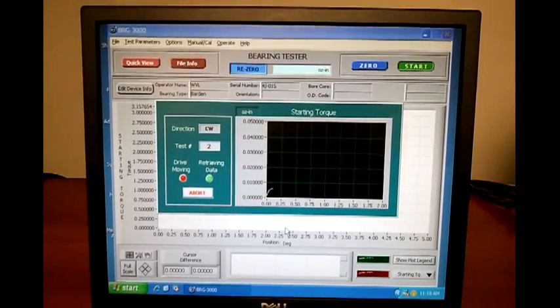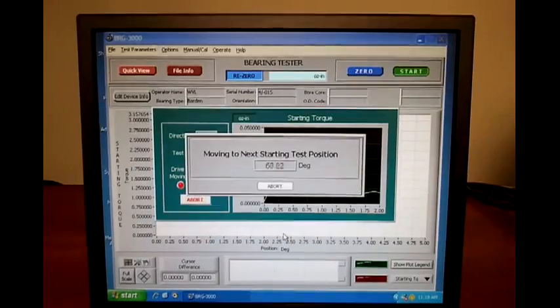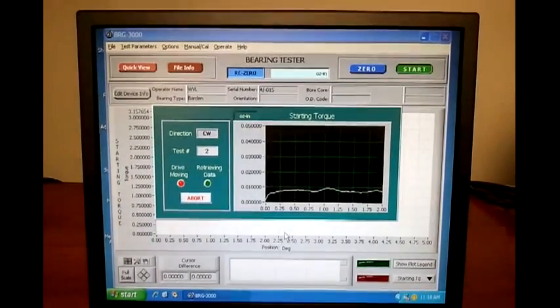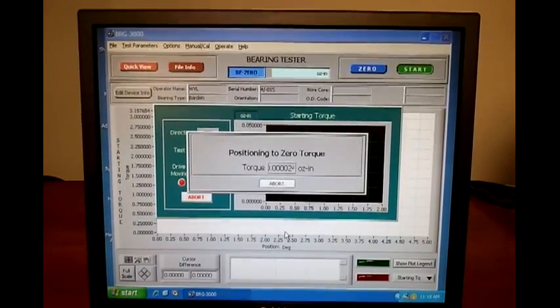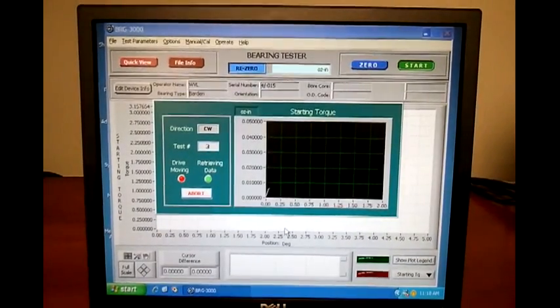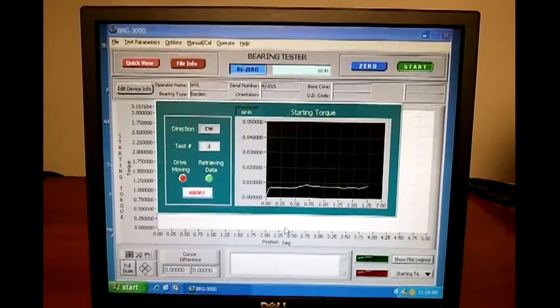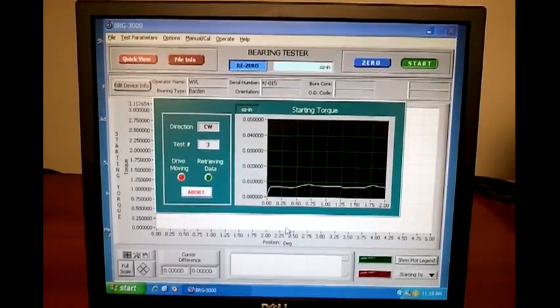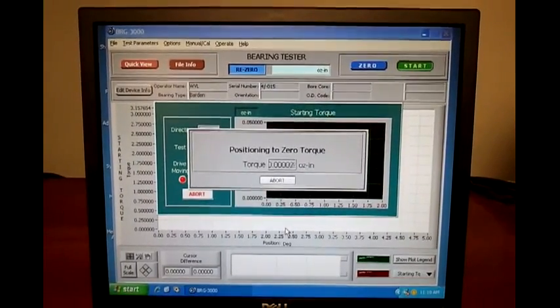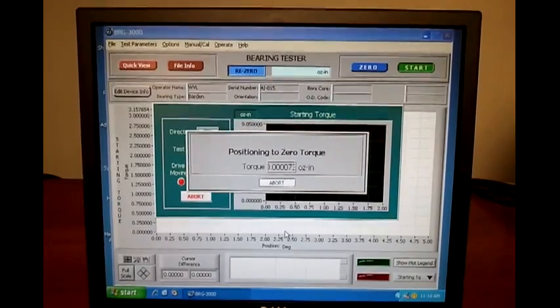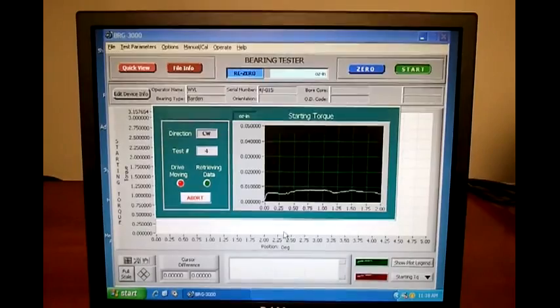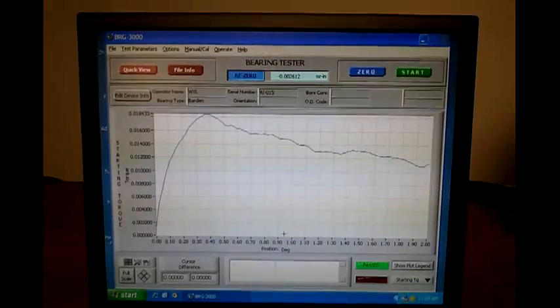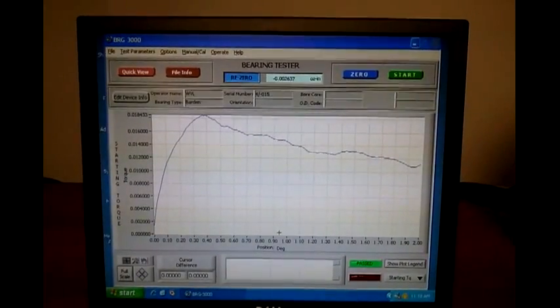It is going to perform four tests, each 90 degrees apart, to determine what the starting torque of the bearing is. Once again zeroing, performing the test, indexing to the next position, zeroing, performing the test. At the end of the test, the highest peak is displayed on the screen.